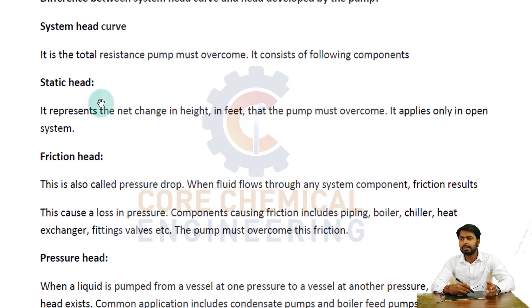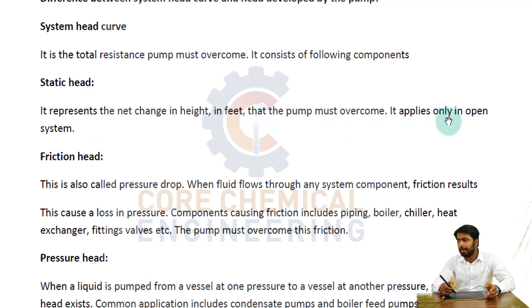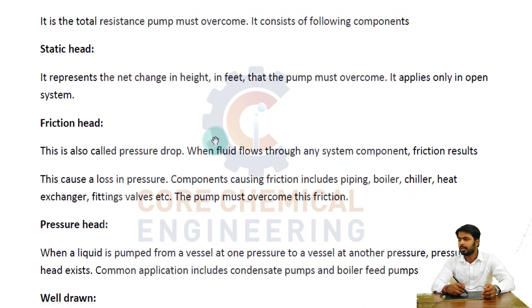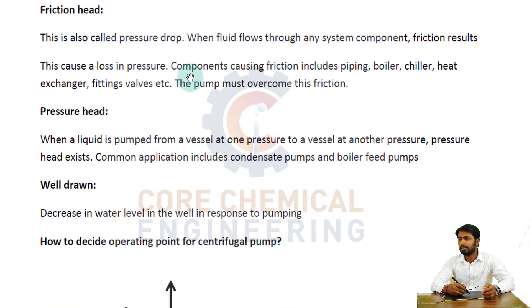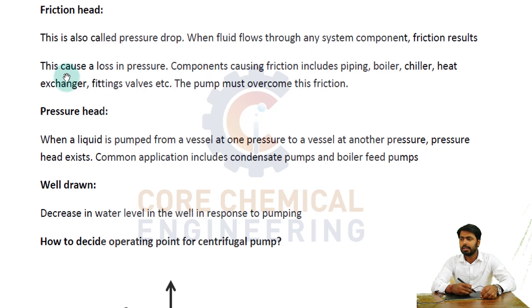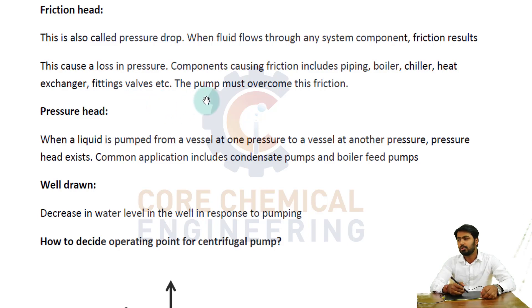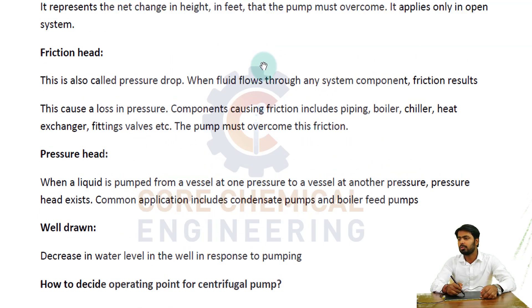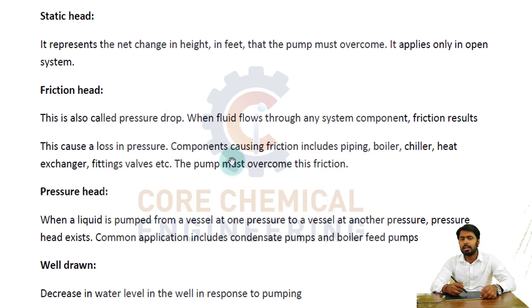Static head represents the net change in height in feet that the pump must overcome. It applies only in open systems because in a closed system static head would be zero. Friction head — also called pressure drop — occurs when fluid flows through any system component. Friction causes loss in pressure, and the components causing friction include piping, boiler, chiller, heat exchanger, fittings, valves, etc. The pump must overcome this friction as well.